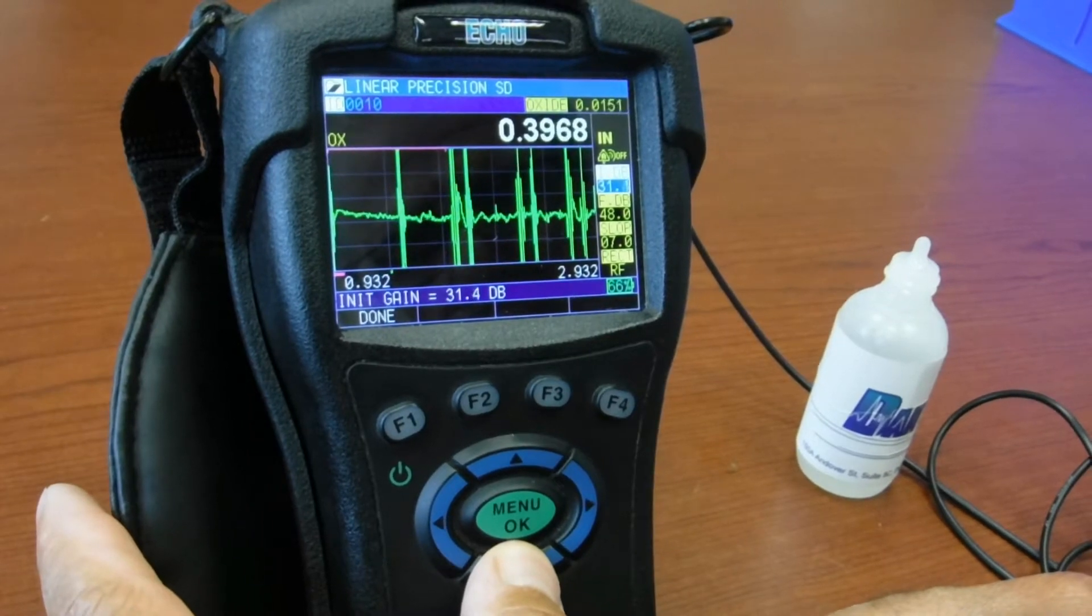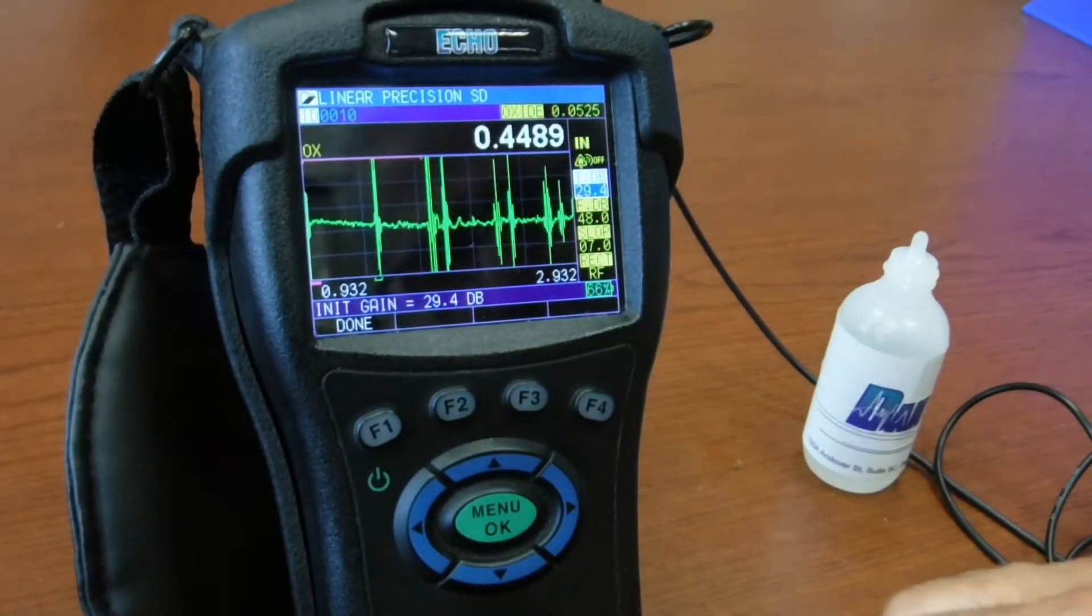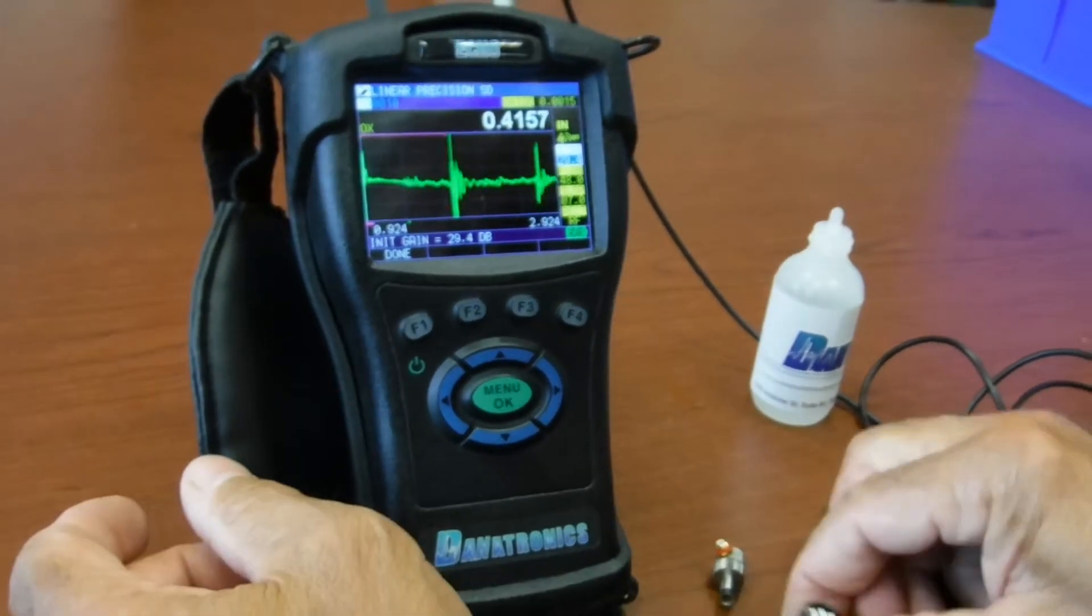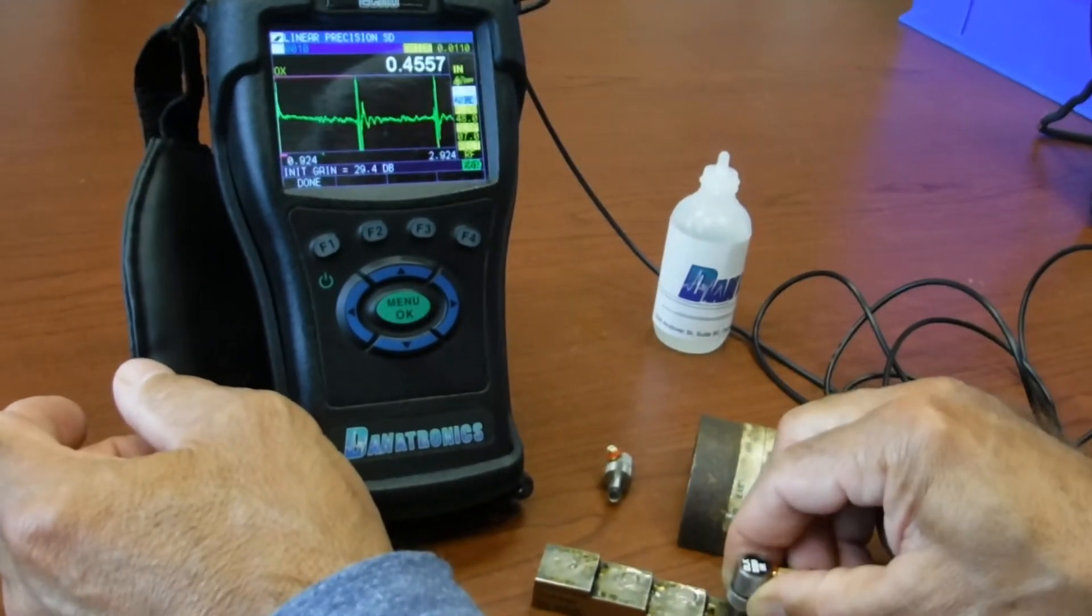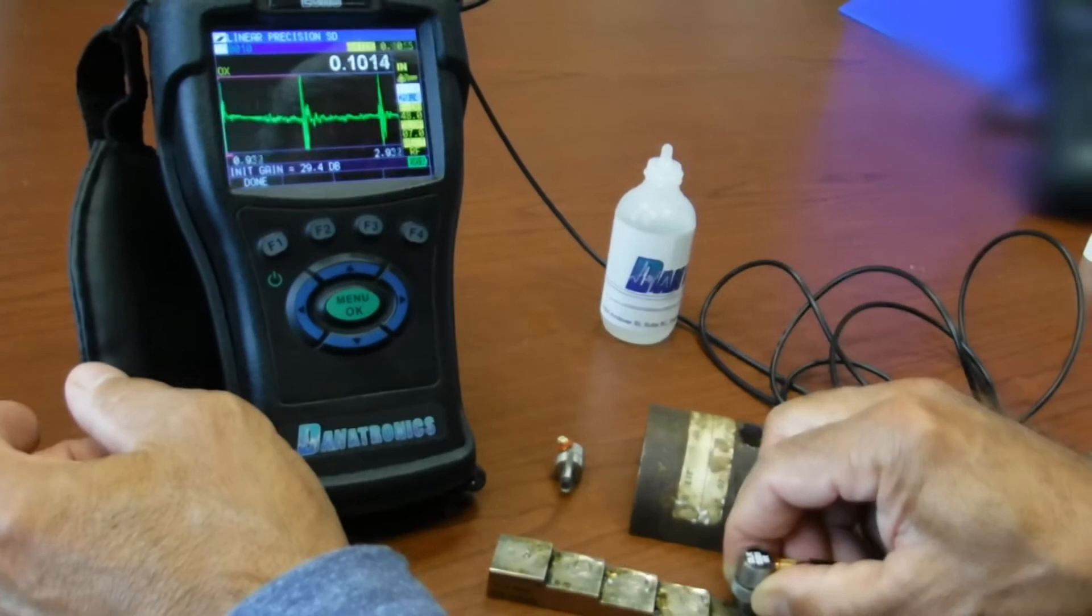Again, I'm on the 500 thousandths, lowering the gain, getting in the ballpark, checking the values before I do a proper two-point calibration. OK, these all look good at this point.